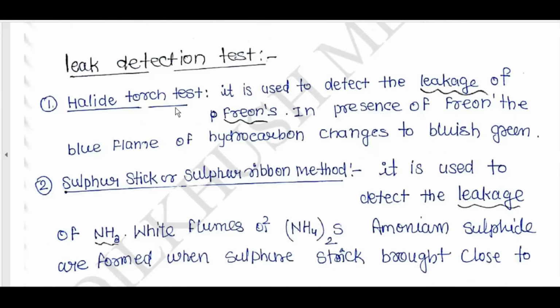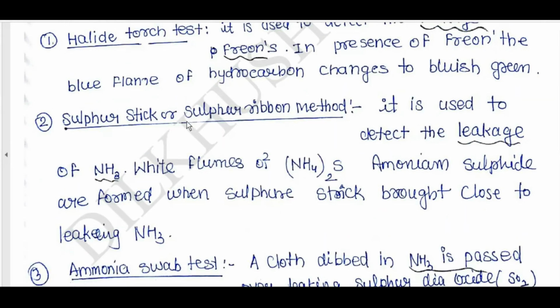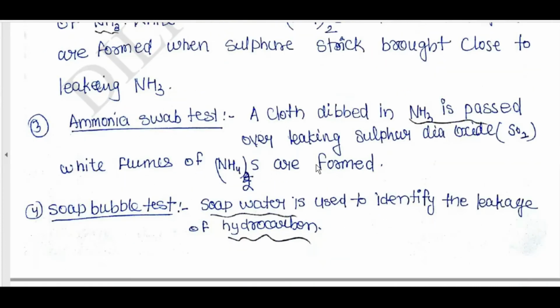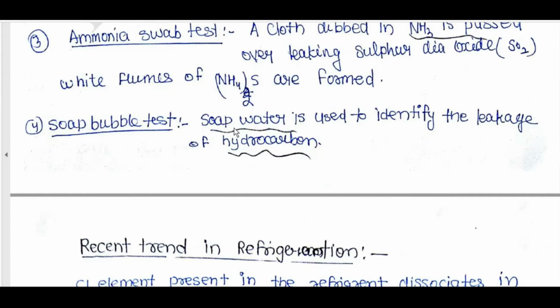Leak detection. Halide torch test is used to detect leakage of freons. In presence of freons, the blue flame of the hydrocarbon changes to bluish green. Sulfur stick or sulfur ribbon test is used to detect leakage of NH3. White fumes of ammonium sulfide are formed when a sulfur stick is brought close to NH3. Ammonia swab test: a cloth dipped in NH3 is passed over leaking sulfur dioxide, SO2. White fumes of (NH4)2S are formed. Soap bubble test: soap water is used to identify the leakage of hydrocarbon.